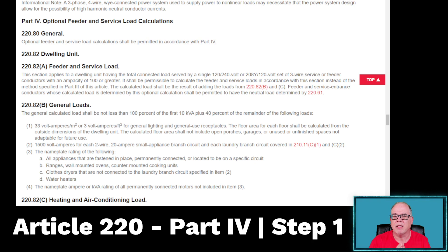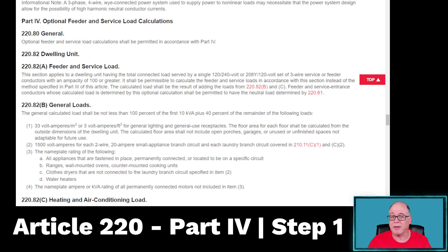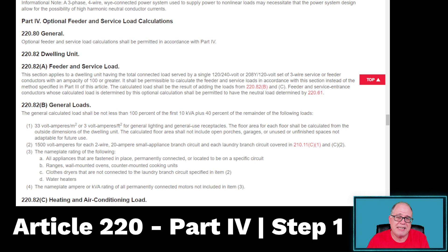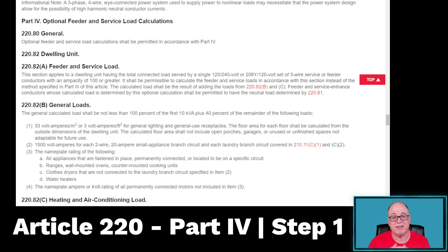The reason we teach the standard method is because when you're sizing a neutral, as you can see in the last line of 220.82A, the optional method permits you to size the neutral loads based on 220.61. Well, 220.61 is not located in Part 4 — it's actually located in Part 3, which is the standard method. So you have to know how to do the standard method in many cases to size the neutral load. There is an exception: if you're using 310.12, which is the 83% rule, then you can size your neutral based on that. But at the end of the day, it still has to handle the maximum unbalanced load, so you have to do a calculation.